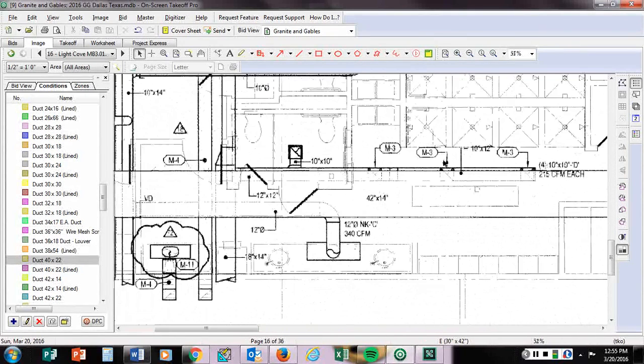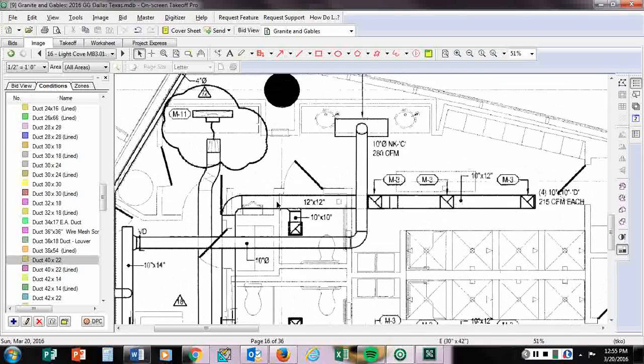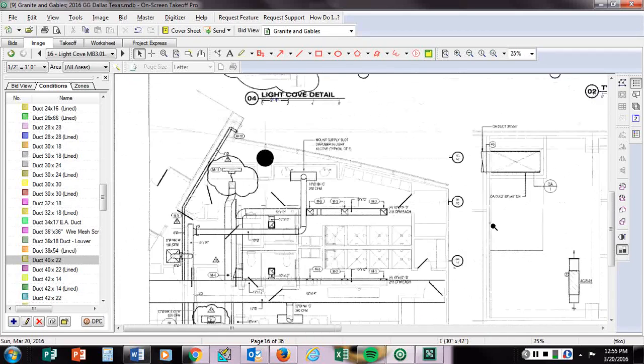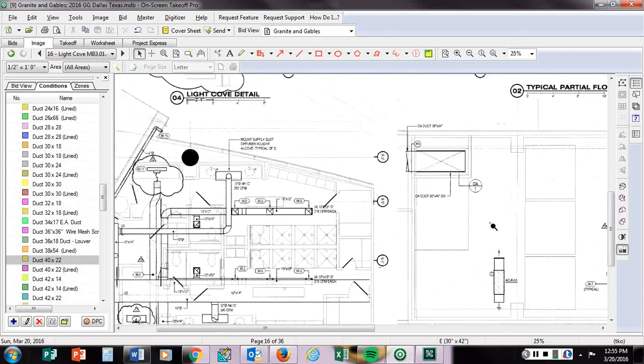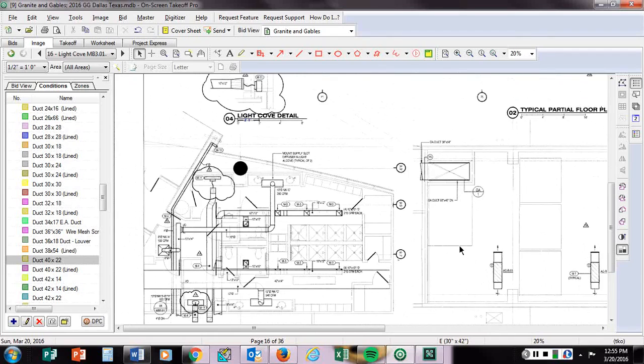You should be able to see in here, it's going to be 12 by 12 duct with a 10 by 10 takeoff, and then there are D registers at 215 CFM apiece. We're not going to be able to do too much with this. There's probably going to be a small drop, maybe a foot on the high side, then right to the register. It's not detailed anywhere, kind of difficult to take off a little bit, so you may have to add a little ductwork there.